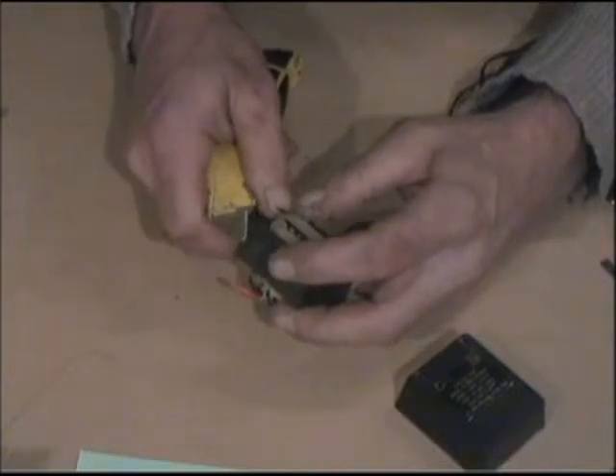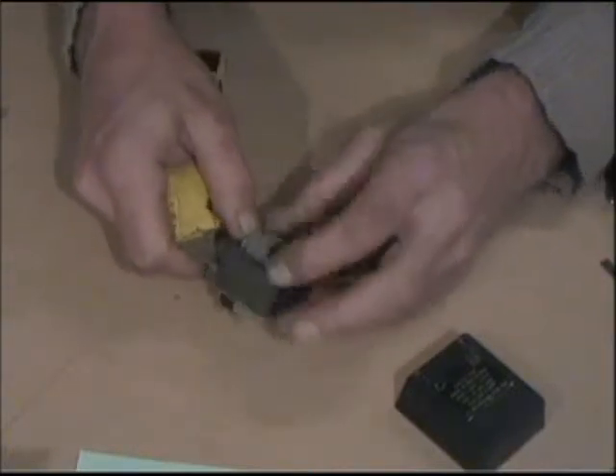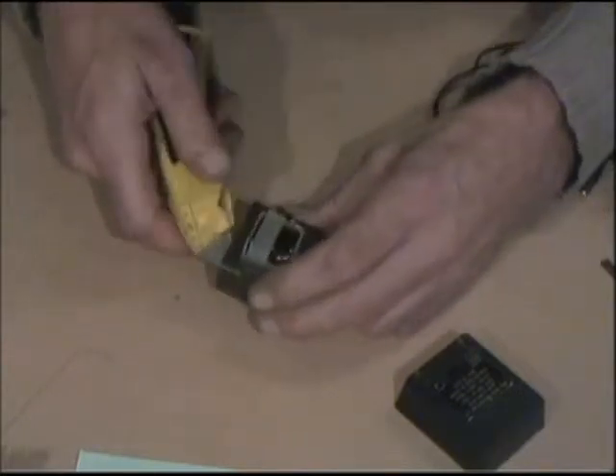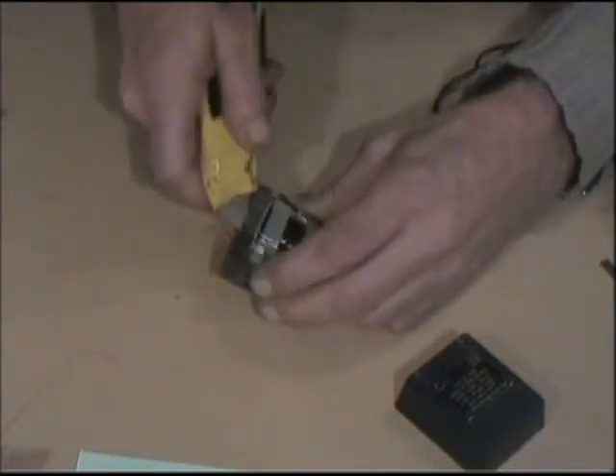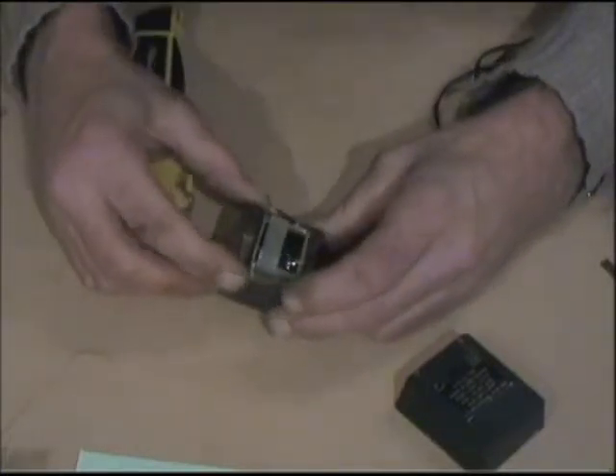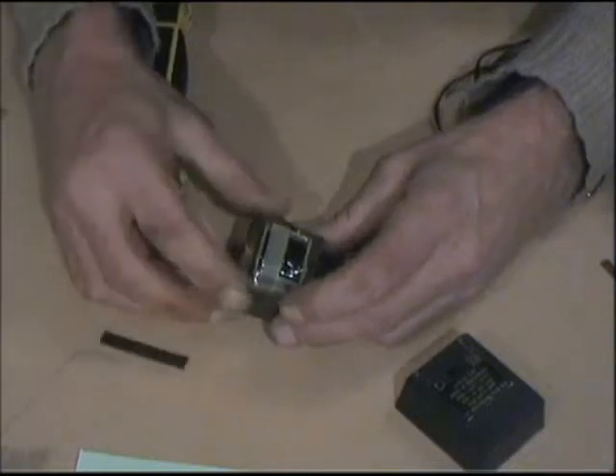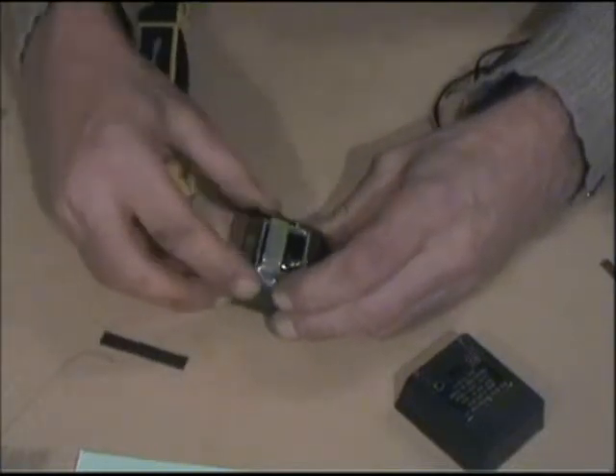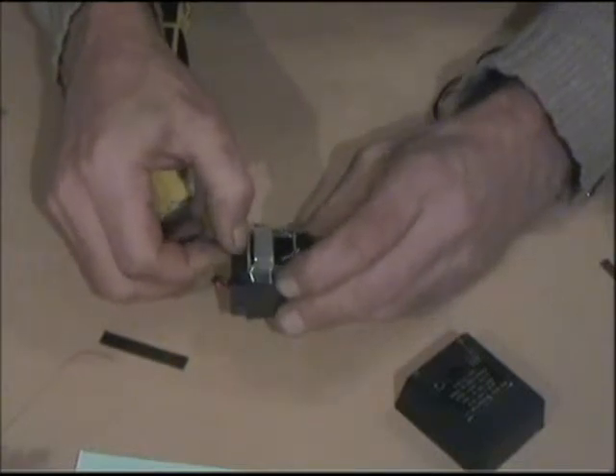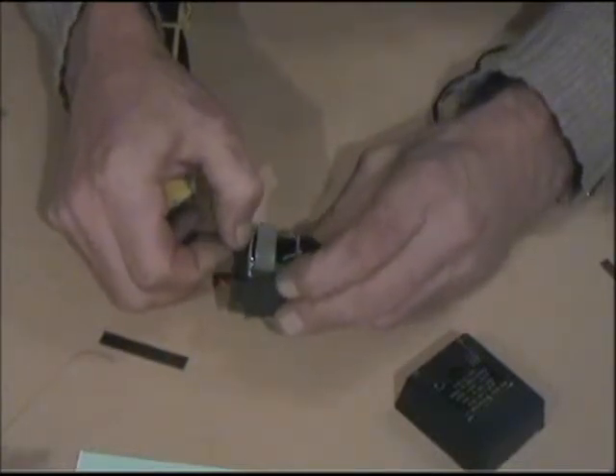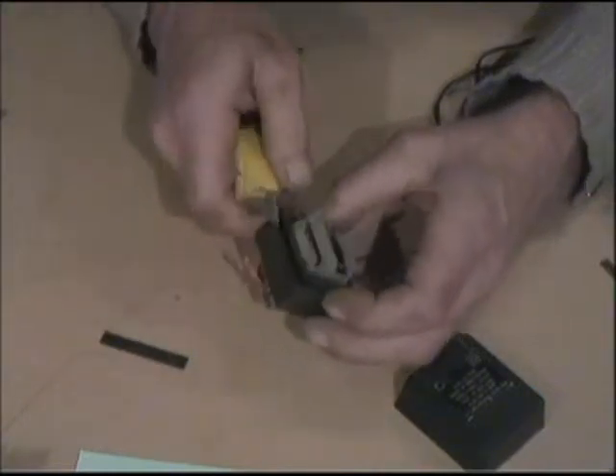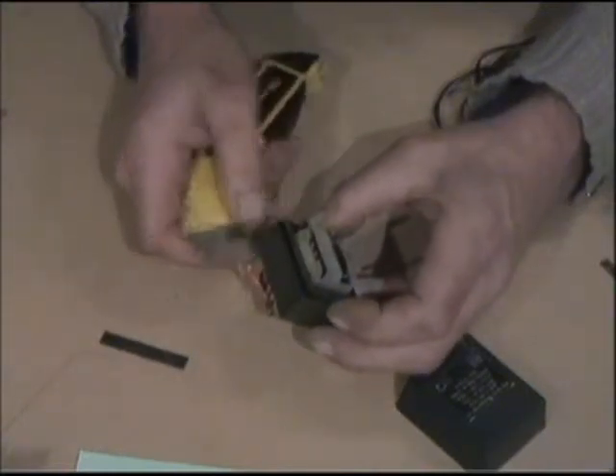If you lift up one of the corners and bend it up slightly, you can get some pliers on there. As you can see, it's starting to fall apart already. Start pulling these laminations out. You might need pliers or pipe grips to get the first one out. Once you get going, work your way down.